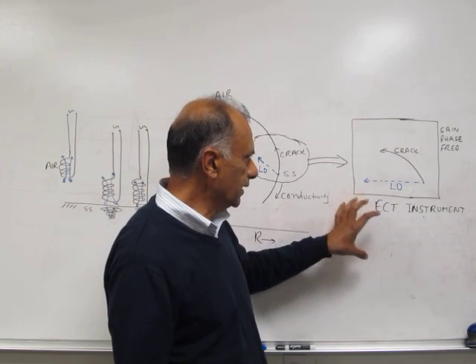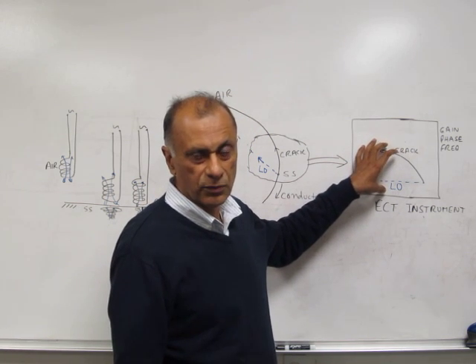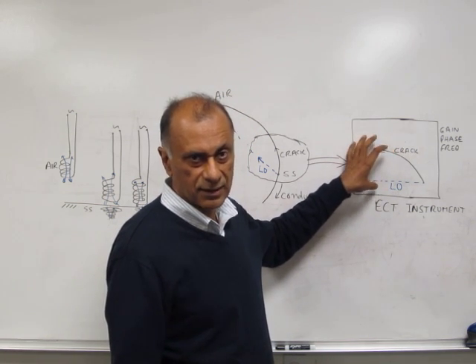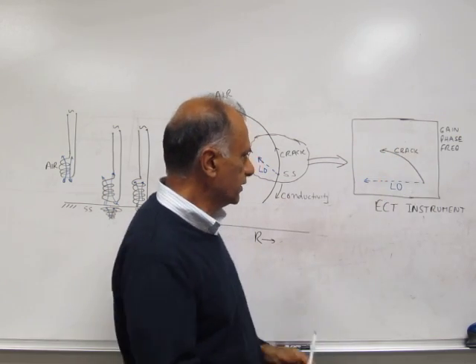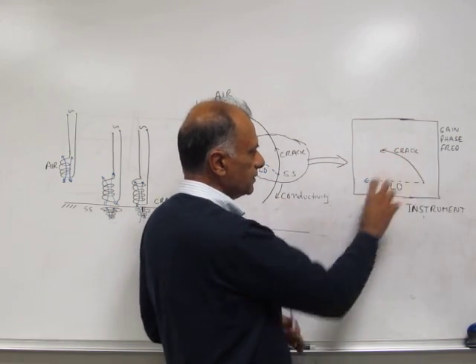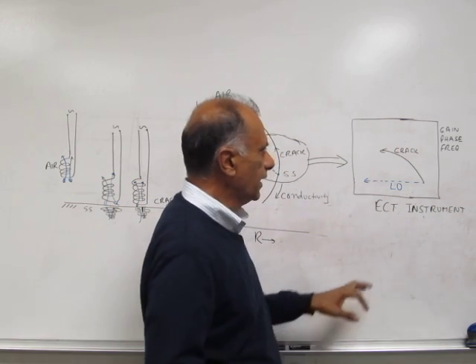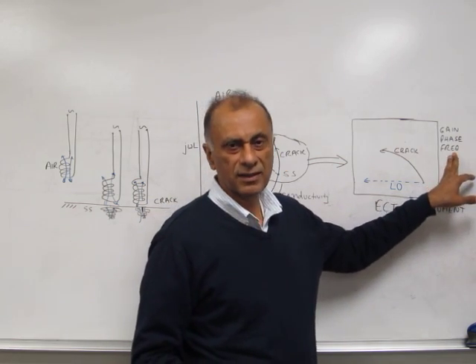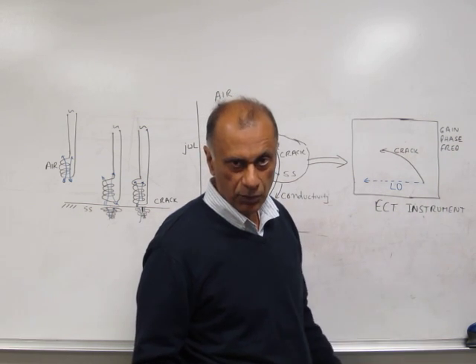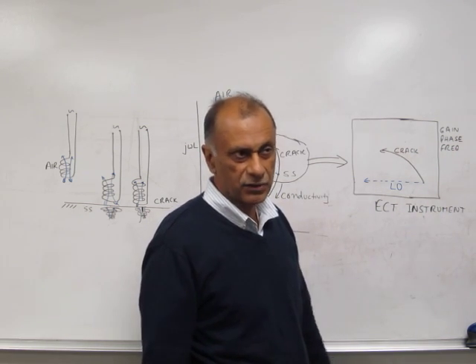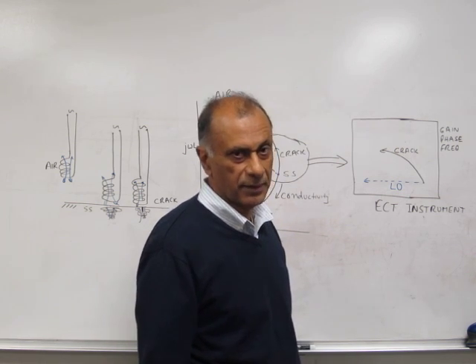The basic controls on the eddy current instrument are: gain, which is used to increase or decrease the signal level; phase, which is used to rotate the signals in order to bring the lift-off to horizontal; and frequency, which is matched to the frequency of the probe — normally in the range of 50 kilohertz to 1 megahertz.